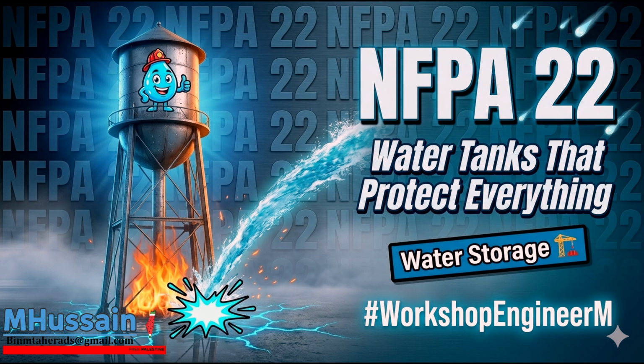By using 4 90-degree elbows arranged in a specific geometric configuration, you create a physical mechanical hinge in the hard piping. Ah, hinge. As the long vertical run of pipe expands and gets longer, those elbows pivot and rotate slightly on their threads or grooved couplings. They absorb the extreme torsional and bending stress of the expansion, translating the linear growth into rotational movement. It isolates the tank connection from the movement of the pipe. You were using geometry to defeat the violent physics of thermal expansion.